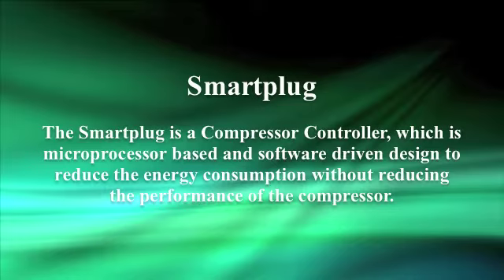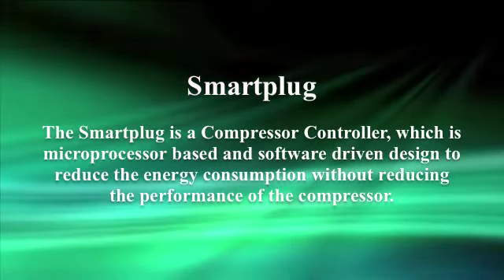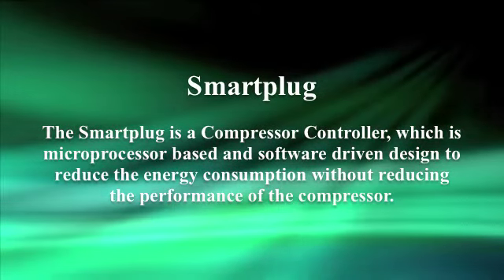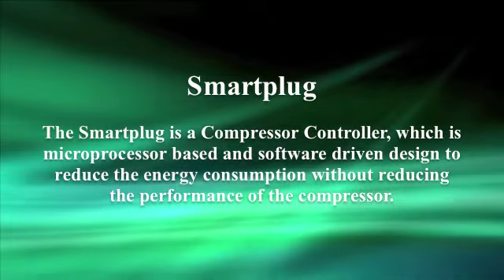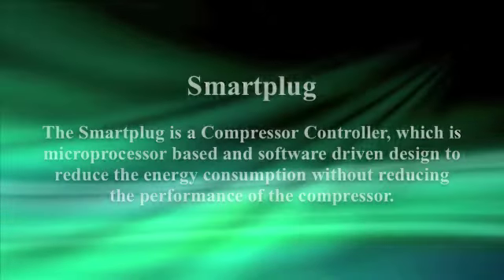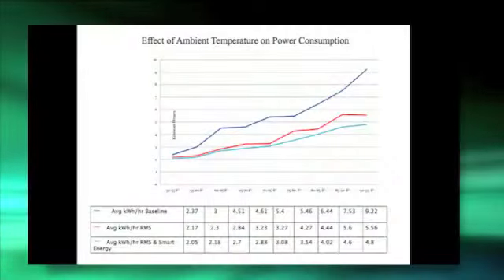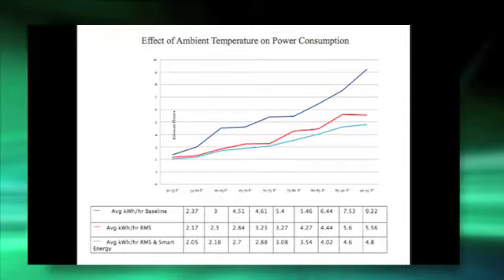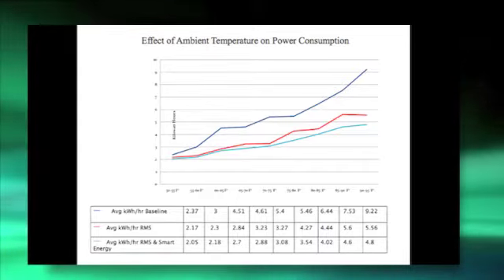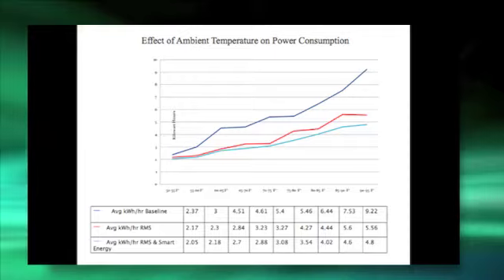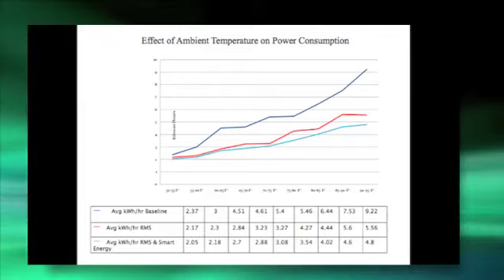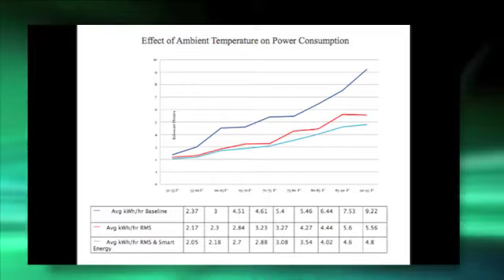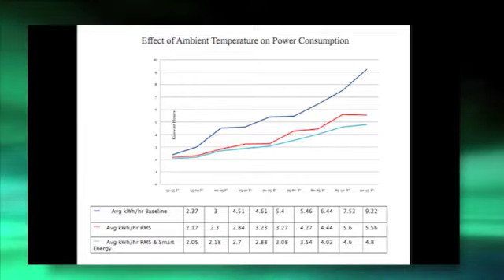The Smart Plug is a compressor controller which is microprocessor based and software driven, designed to reduce the energy consumption without reducing the performance of the compressor. The blue line at the top shows the effects of the ambient temperature on power consumption without our systems installed. The red line shows the effects with the Articmaster and RMS-1, and the light blue line shows the effect with the addition of the Smart Plug.